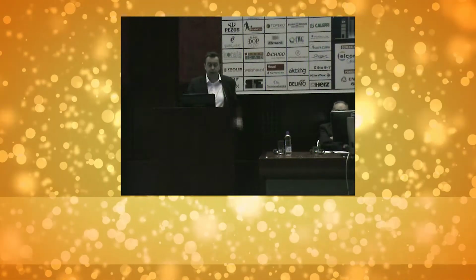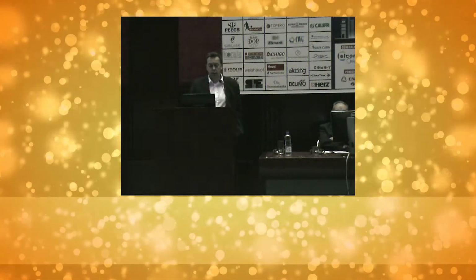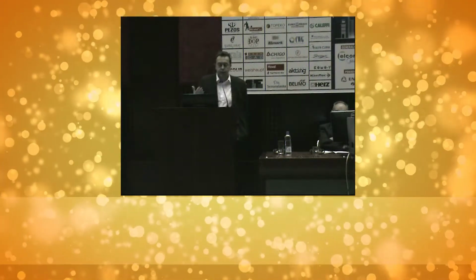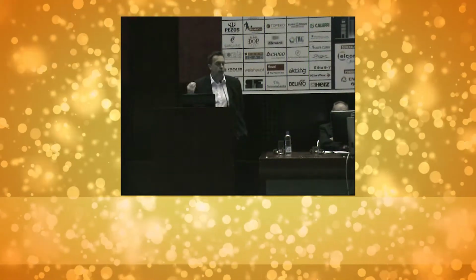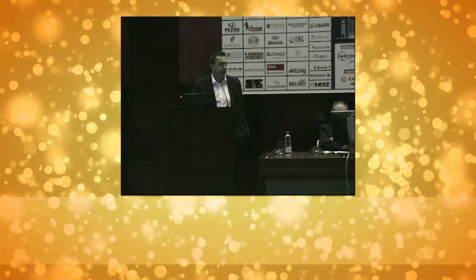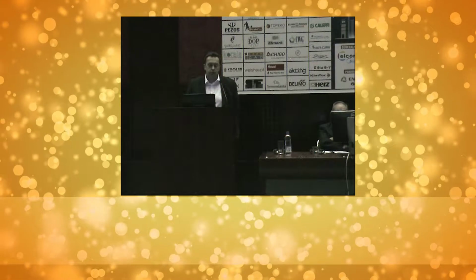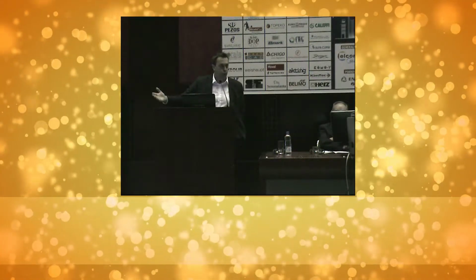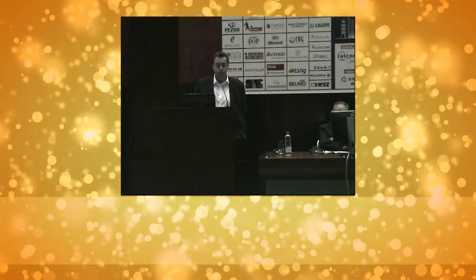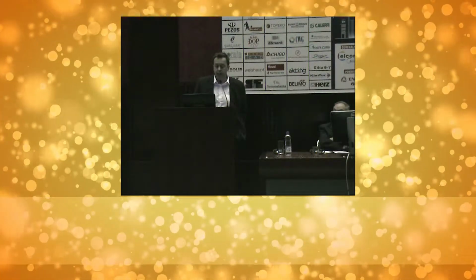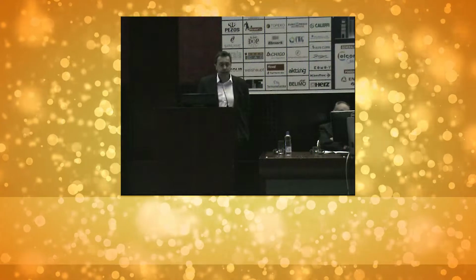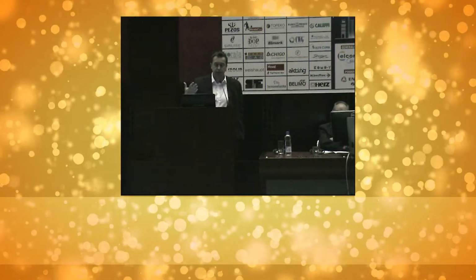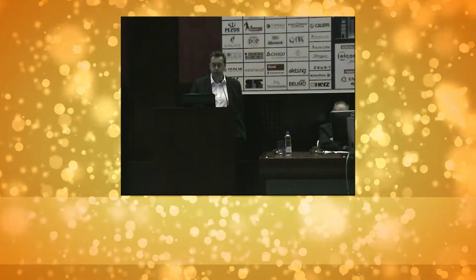We mentioned earlier, in some of the previous speakers, air changes per hour, and generally these are rule of thumb, I call them guides. If a building is very tightly well made, sealed, you're probably only going to get half an air change an hour naturally. If you have a building that's pretty loose or old, or you've got the windows and doors open a lot, you've probably got at least 2 air changes an hour, sometimes 3, depending on the outside conditions. And obviously any mechanical ventilation has got to be dictated by the fan performance in terms of the air movement.